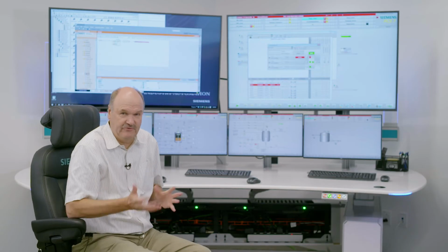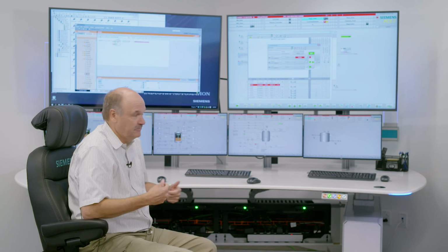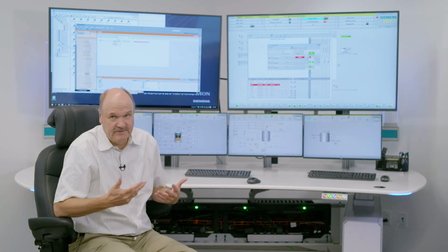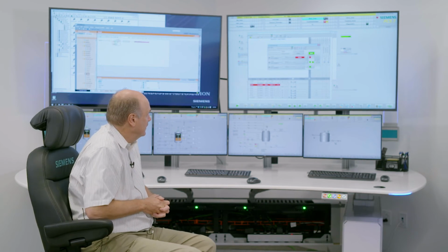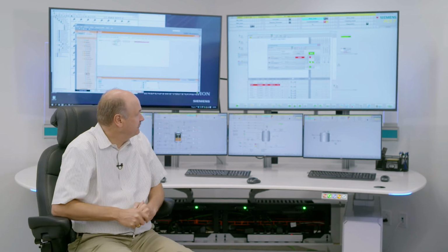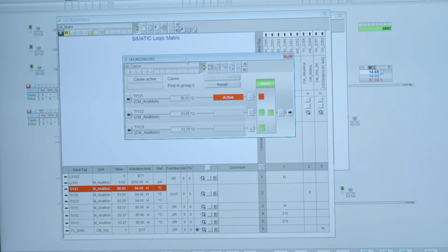So the second measurement now is undergoing its value change, and that will show you two things. One is the 2 out of 3 works, like here, but as soon as the second measurement reports a process upset, the effect will be triggered. Visible in the detailed view that I've popped up, but also as you can see in the list.